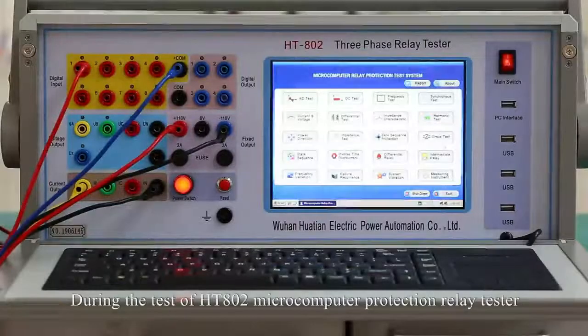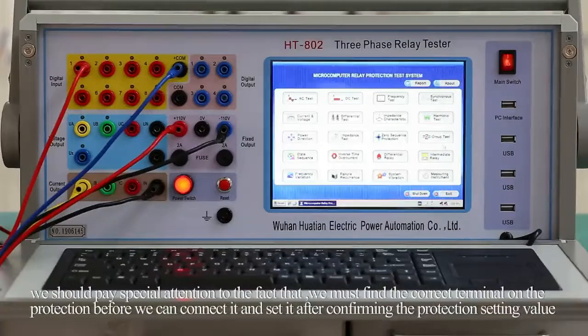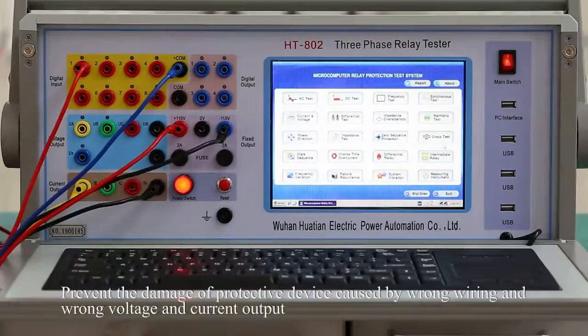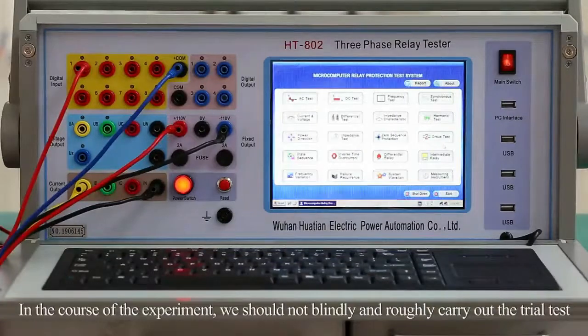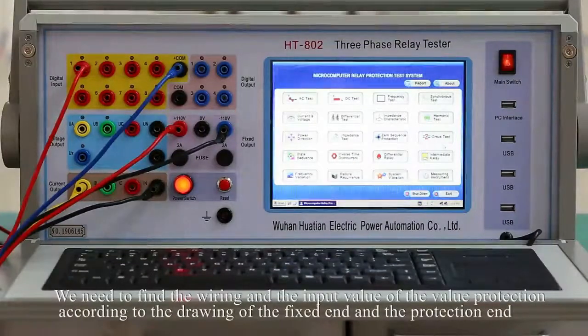During the test of the HT802 protection relay test set, we should pay special attention to the fact that we must find the correct terminal on the protection before we can connect it, and set it after confirming the protection setting value. This prevents damage to the protective device caused by wrong wiring and wrong voltage and current output. In the course of the experiment, we should not blindly or roughly carry out the trial test. We need to find the wiring and the input value of the protection according to the drawing of the fixed end and the protection end.